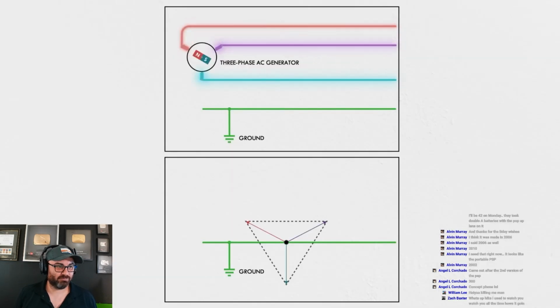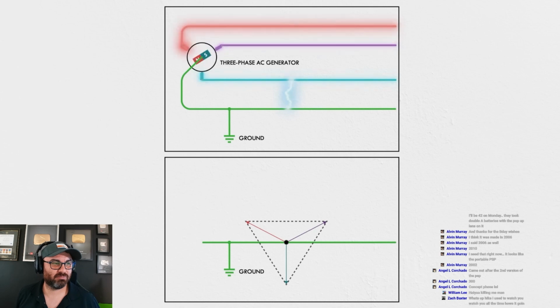But in the case of substations and transmission lines, the fault current path is the actual ground. Let's look back at the diagram and convert it to a grounded system. If I add a strong bond to the ground at the generator, things don't look much different in the unfaulted condition. But as soon as you add a phase to ground short circuit, the diagram looks much different. First, the other phases don't experience a shift in their phase to ground potential. But secondly, there's now a path for fault current to flow through the ground back to the source. And that's the answer to the question in the title of the video.